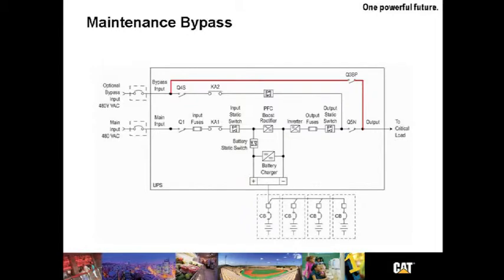Let's talk about maintenance bypass. The CAT UPS B130 has a distinct advantage in that it offers an internal maintenance bypass. This allows the load to be powered by the utility or genset while being serviced. Most UPS offer only an external maintenance bypass option. Of course, we recommend having the system on generator power prior to doing any service to assure continuous power while servicing the UPS. It would be a tragedy to have the utility fail while you're doing your normal UPS maintenance. Thus, coordinated service calls is yet another good reason for purchasing the entire system from Caterpillar.